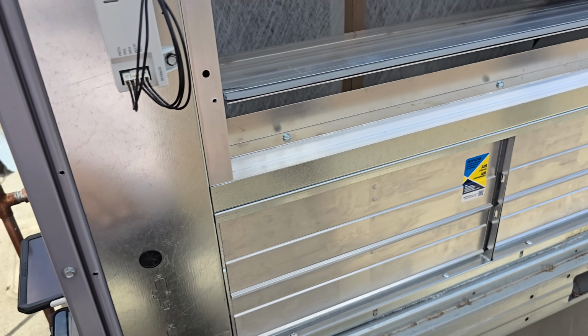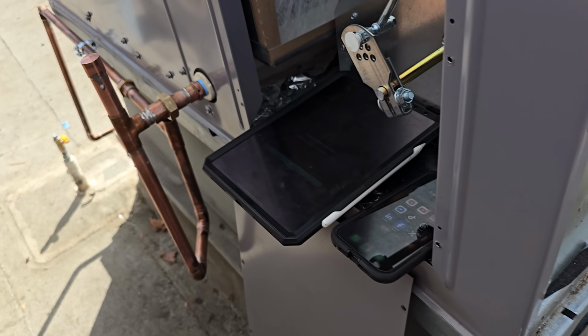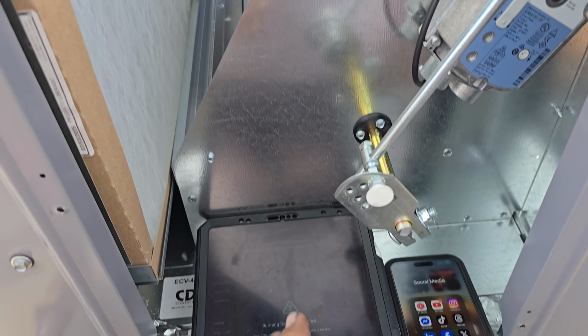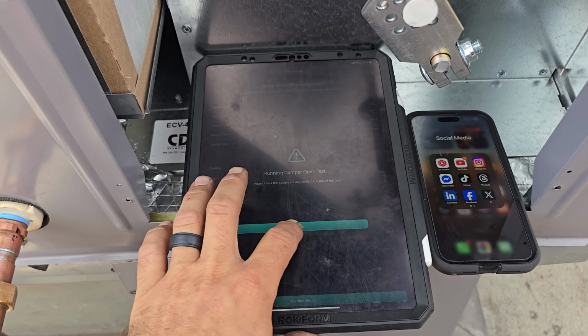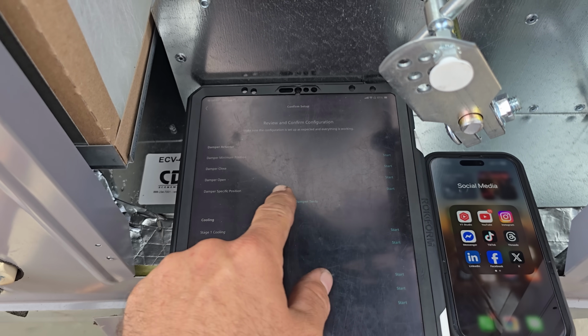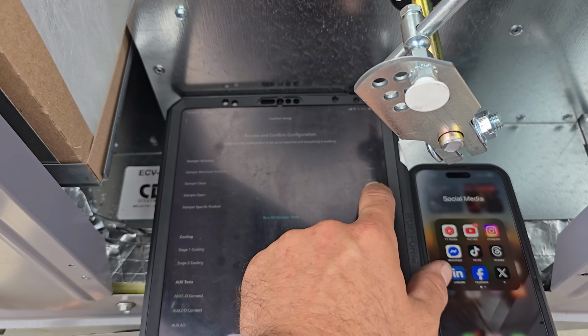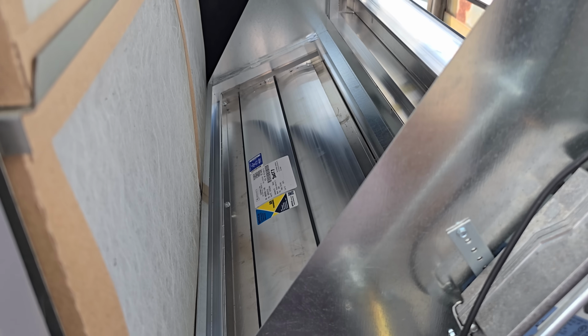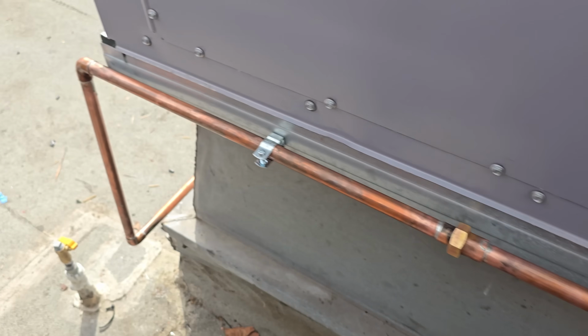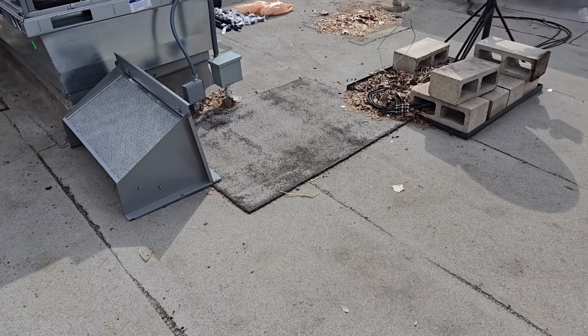So we got this guy wired in, set up, currently commissioning the economizer, making sure that the damper closes, so we're done, that's the damper test. And then now we want damper open all the way, start. So we're gonna do the opposite test.